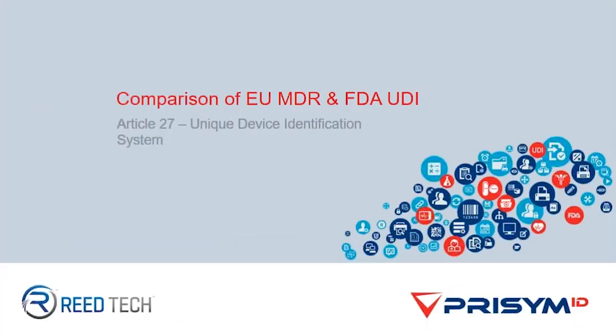So let us move on to the subject of UDI. The UDI requirements get a whole section, a whole article to themselves within the EU MDR regulation. Article 27 talks solely about the UDI requirements. If you have already implemented UDI to meet the FDA compliance, then you'll recognise how significant a change this can be.